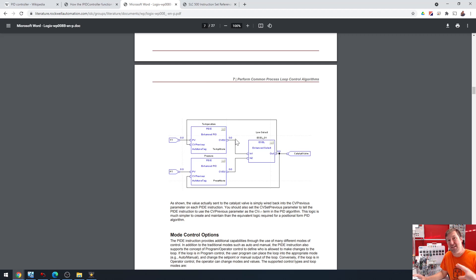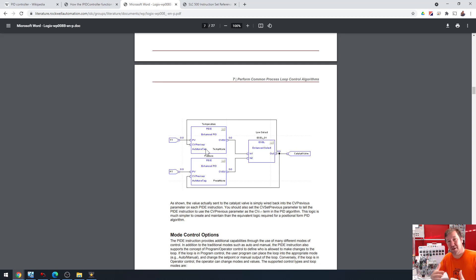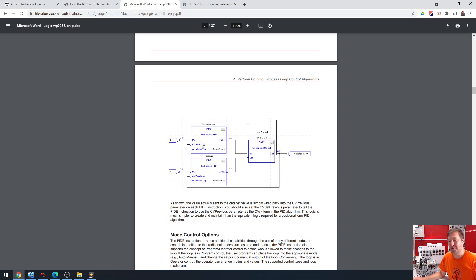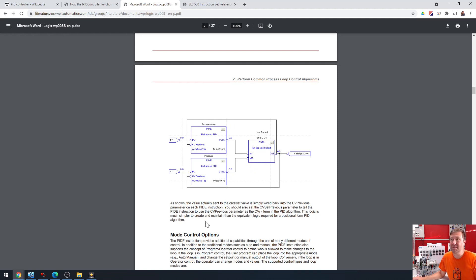So it is temperature and pressure. We can combine these two outputs, then we can choose the lowest of the two of them. And then we can feed whichever one we ended up with back into the front of that PIDE. So it gives you a tremendous amount more flexibility.